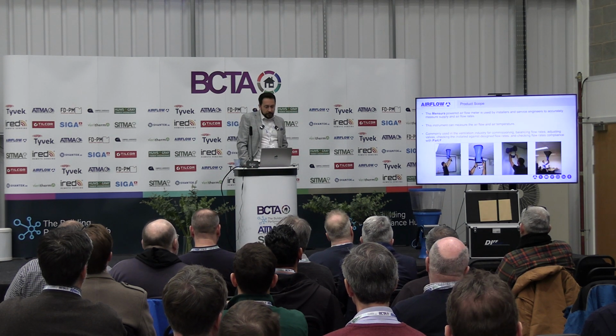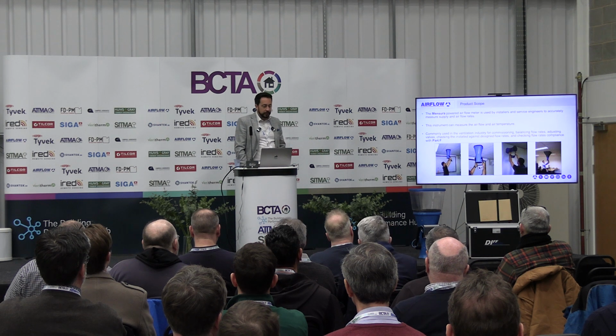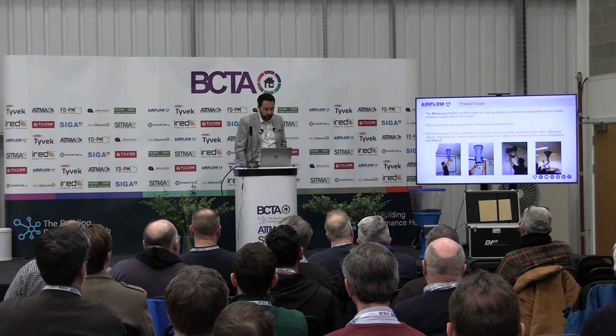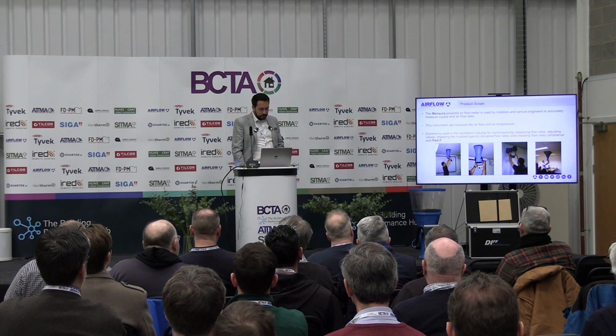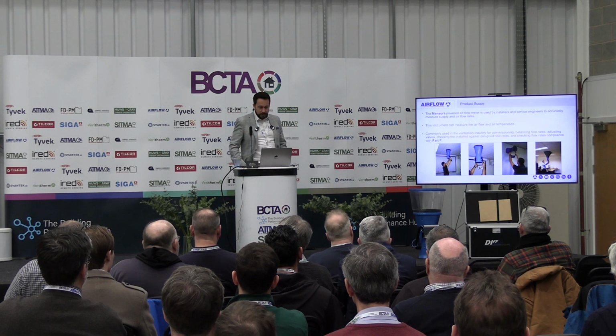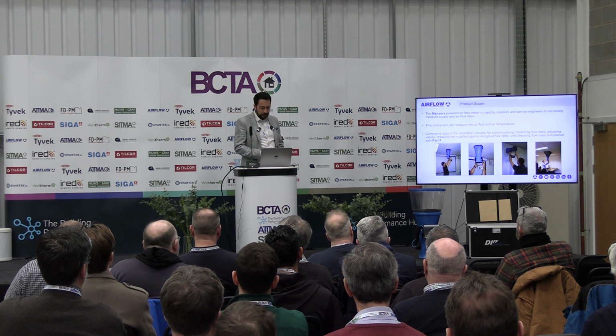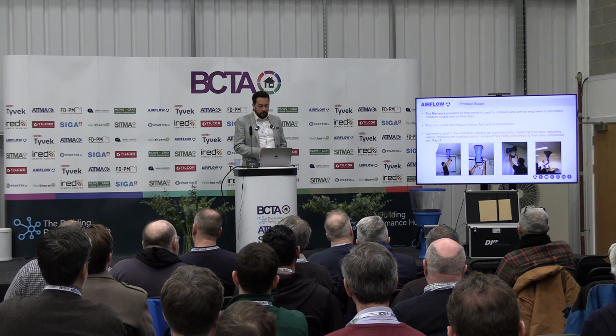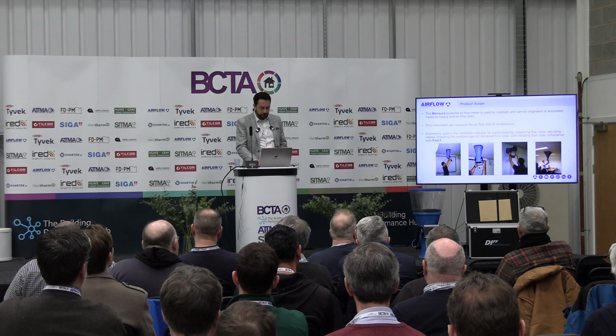So yeah, it's mainly for installers and service engineers, to accurately measure the supply airflow rates. The instrument can measure the airflow and the temperature, and it's commonly used in the ventilation industry for commissioning, balancing flow rates, adjusting the valves, checking the installed against design flow rates, and checking the flow rates in compliance with Part F of the building regulations.